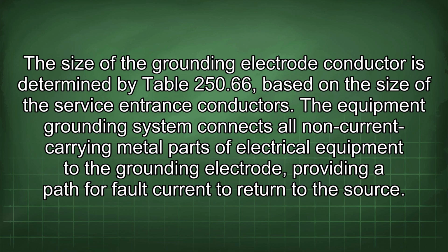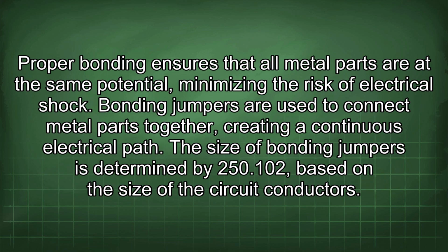The equipment grounding system connects all non-current carrying metal parts of electrical equipment to the grounding electrode, providing a path for fault current to return to the source. Proper bonding ensures that all metal parts are at the same potential, minimizing the risk of electrical shock. Bonding jumpers are used to connect metal parts together, creating a continuous electrical path. The size of bonding jumpers is determined by 250.102, based on the size of the circuit conductors.